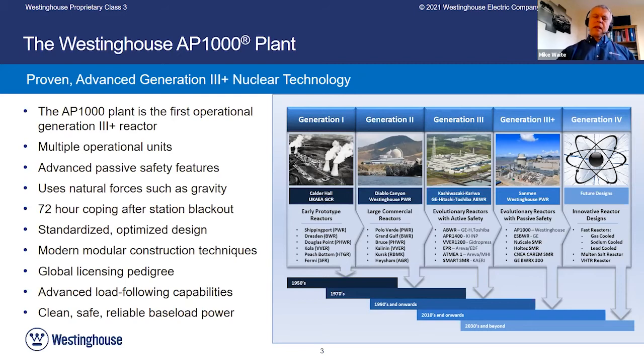So let's talk a little about that station blackout. That is basically what happened at Fukushima. If we remember back to that incident, which really reset the nuclear industry for some time, the reactors actually shut down perfectly after the earthquake. All the safety systems kicked into gear, but when the tsunami hit, the diesel generators supporting all those safety systems, pumps, and motors became inoperable, and the reactors were then allowed to overheat.